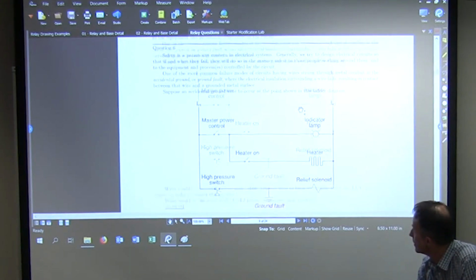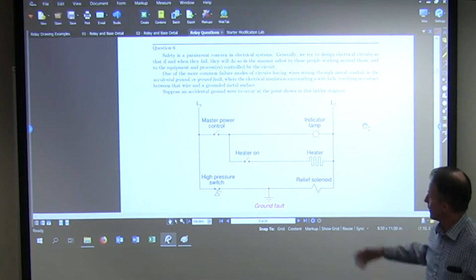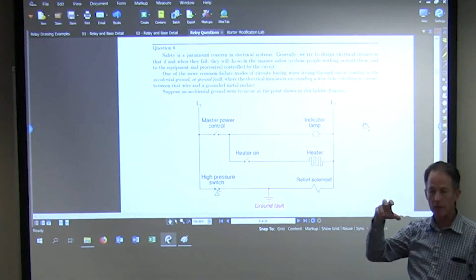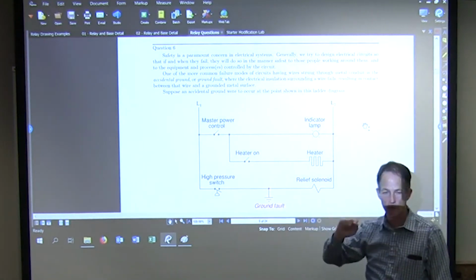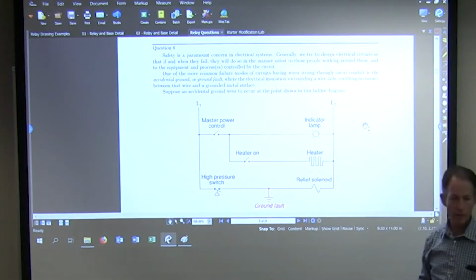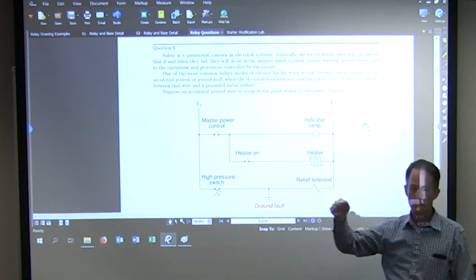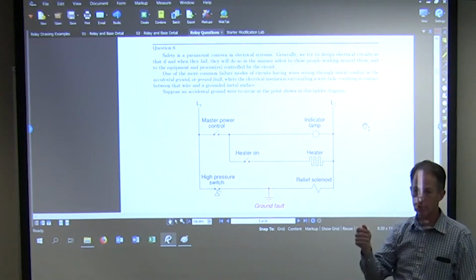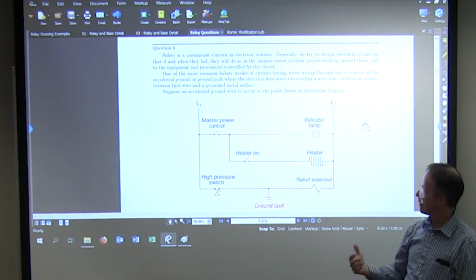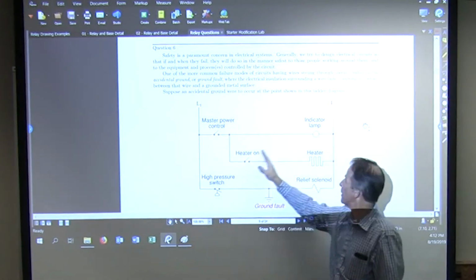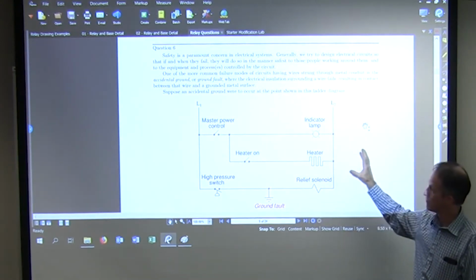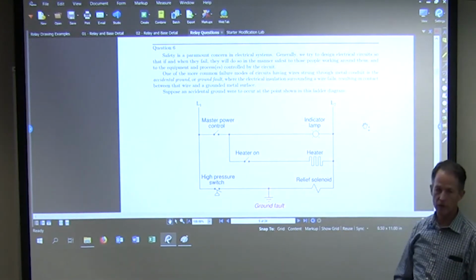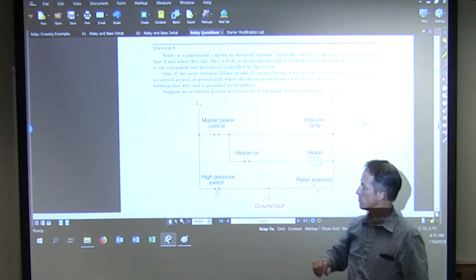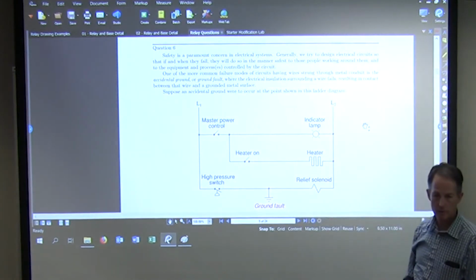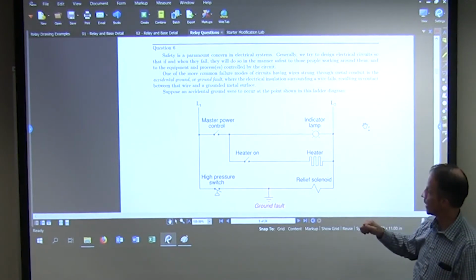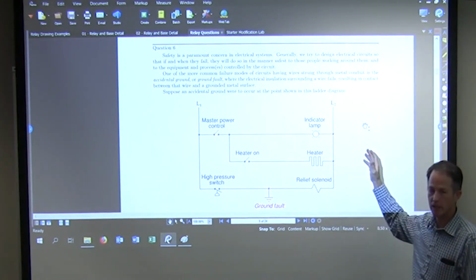Let's see here. So here's one where we have that same circuit, and let's talk a little bit about what happens if we introduce a ground fault. Ground fault means the wire here somehow is rubbed through and is touching something that goes to ground. Now, if I have 120 volts on L1 and neutral on L2, and this isn't powered, the switch isn't made, is there going to be any problems? No. Okay. Not yet. So I turn on my master control power, still no problem. I turn my heater on, the heater starts heating, still no problem.